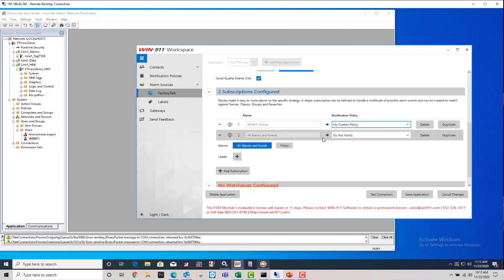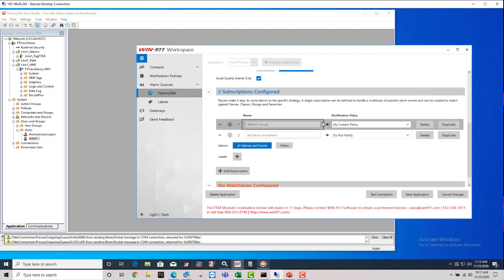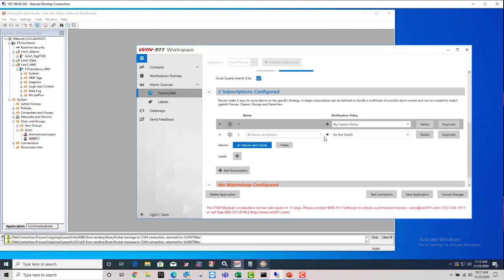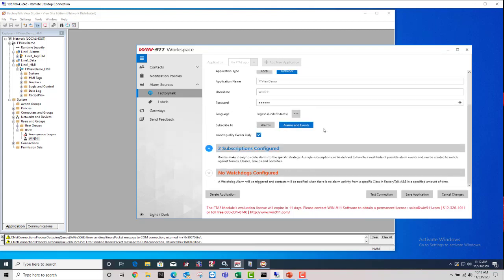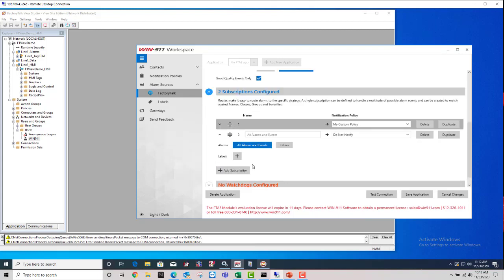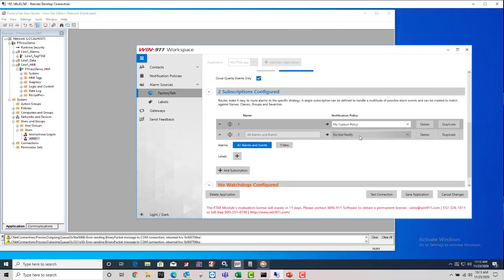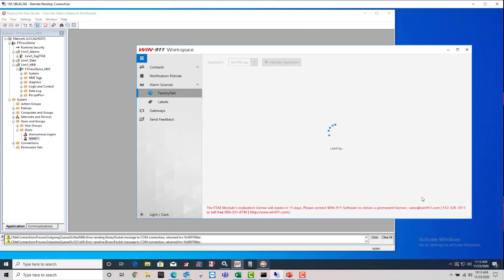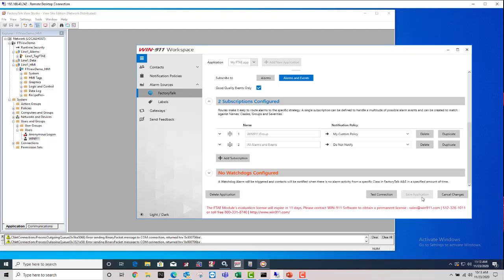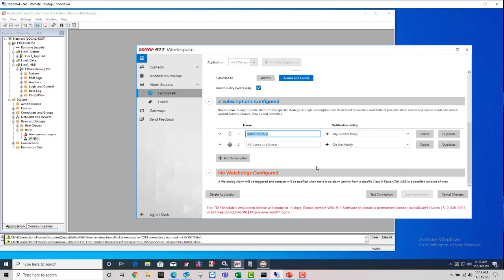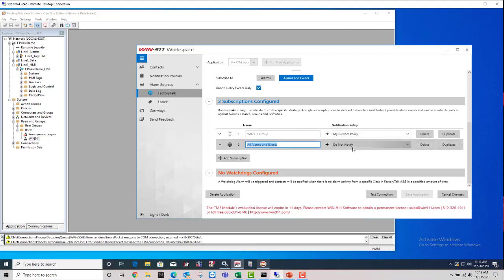So the reason I recommend adding this all alarm and events is that if this filter isn't working right or the alarms aren't getting caught by it, maybe there's an issue with the filter criteria you've created, we're not going to see any of the alarms with just this first line because we're not matching correctly for those. And what I would recommend doing is keeping this all alarms and events filter in here so that you can at least see in the log viewer that the ones that are not getting caught by this subscription are going to be caught by everything else, right?